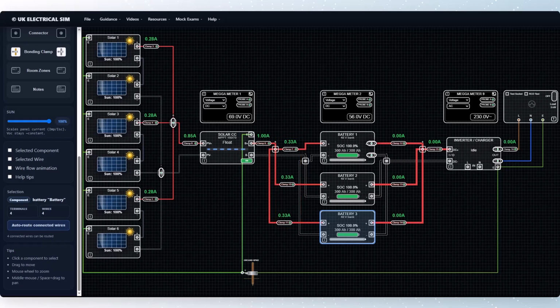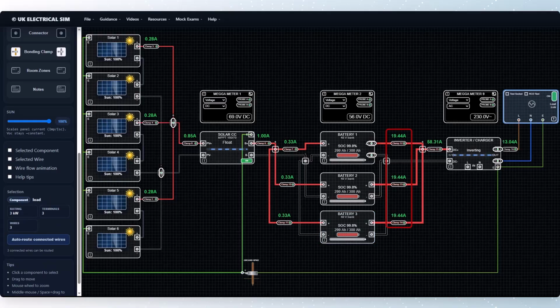We are now in float mode, with minimal current flow. Let's switch on the load and activate the inverter charger, then watch the batteries start to discharge. We can see current from each battery combining to provide the inverter with almost 60 amps of total DC current. Once the batteries drop below the set return value, such as 97% state of charge, the solar charge controller starts charging the batteries again. However, the 3 kilowatt load is still drawing power. If the solar panels cannot provide enough energy to cover the load and recharge, the batteries will continue to drain.